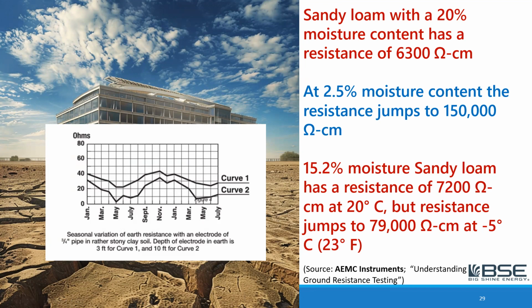And then curve two, you can see they got a very low reading in May. So if you measured it in May that year, you would say, wow, this is a very good grounding system. But look how it does in November and December and January. It's terrible. So it's really important that we understand these relationships so that when we do test, we can interpret the results correctly, because what matters is not whether we can say, oh, we did the test and it passed, but that's passing today. What we want to do is have a facility that's robust and we have sustainability success.